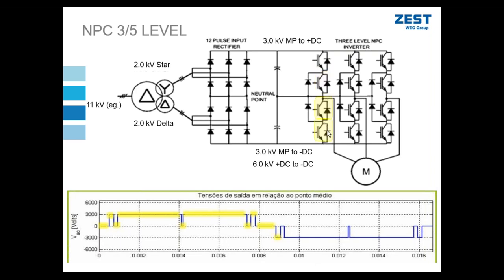I then do the same on the negative side to provide my negative polarity voltage waveform to the motor. And that's essentially what it looks like. Let's just run through that little animation again. Switching the two inside IGBTs in one phase, two outside, back to the two inside, two outside, two inside, two outside, two inside, two outside, two inside. Then the two bottom outside, the inside again, bottom outside, the inside, etc.